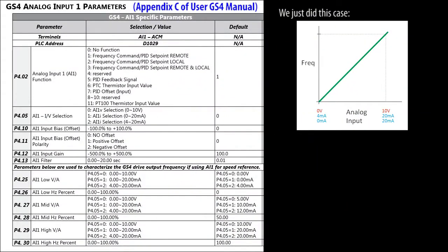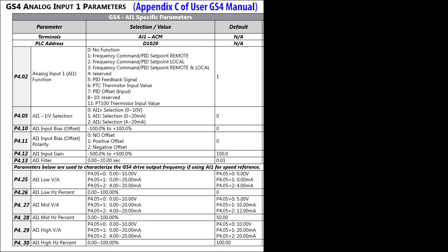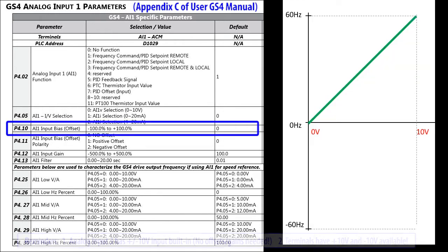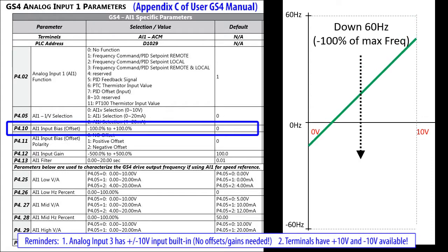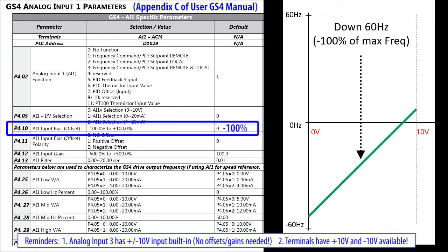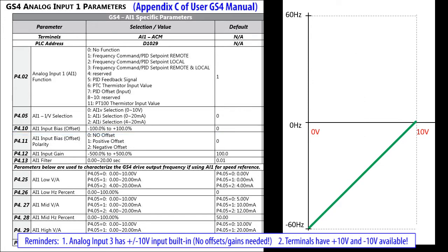What if we wanted to control both forward and reverse — which is plus 60 Hz to minus 60 Hz — from the 0 to 10 volt potentiometer? Example number 4 in the user manual shows us that all we need to do is dial in an offset. We want to shift the curve down 60 Hz or 100% of the max frequency, so I'll enter minus 100 in the analog input 1 offset parameter.